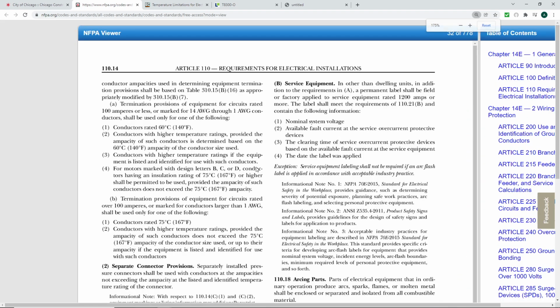And this right here is telling you this particular one. And you can notice that out of all of the 4s, they don't have a temperature column, because I'm assuming that when NFPA created the books, they understood that there's devices that can have a lower terminal rating but have a wire with a certain installation that can have a higher ampacity rating, and then that's why they put that 240.4D overcurrent protection. So it all makes sense now.